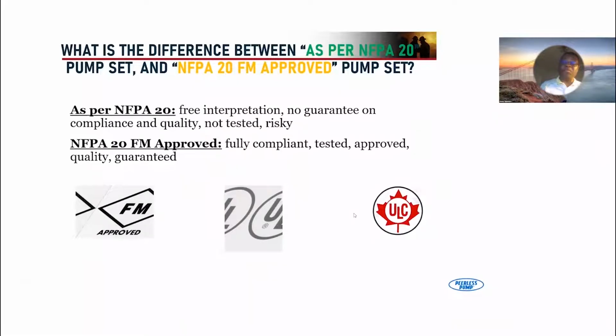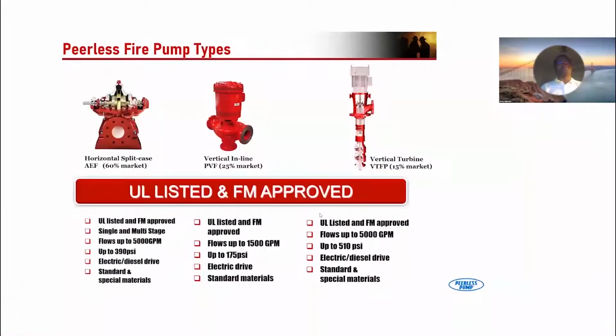But if you do have the UL and the FM sticker on your pump, you can rest assured that the pumps have been stress tested to the limit, where the independent listing authority like FM, UL, or in another case ULC, which is for Canada, have already seen the pump and made sure that it complies fully with the requirements of the code. All right, having said that, those are just my little preamble into that.